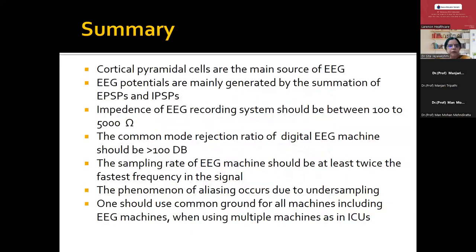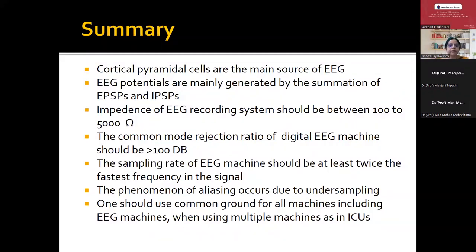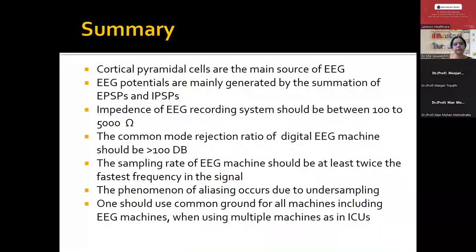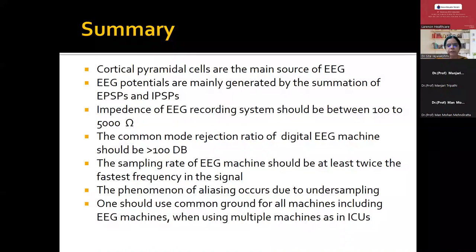To summarize: cortical pyramidal cells are the main source of EEG activity. EEG potentials are generated by summation of excitatory and inhibitory postsynaptic potentials. Impedance of the EEG recording machine should be between 100 to 5000 ohms. One should know the common mode rejection ratio of the digital EEG machine, which should be more than 100 decibels. The sampling rate of the EEG machine should be at least twice the fastest frequency of the signal — that is 70 hertz — so more than 140, but nowadays we get more than 210. The phenomenon of aliasing occurs due to undersampling, so sampling rate should be good. One should use a common ground for all machines, especially in ICU recordings.